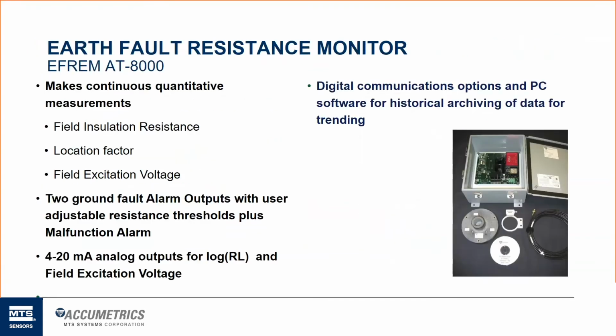So let's talk a little bit about the EFREM system. The EFREM is our AT8000 series piece of equipment. That is the Earth Fault Resistance Monitor is what EFREM stands for. So that provides continuous quantitative measurements of both the field insulation resistance and the excitation voltage. Then what we offer is the location factor, which can help determine when or where on those field windings a ground fault has occurred. And I'll explain how we do that in the next slide.